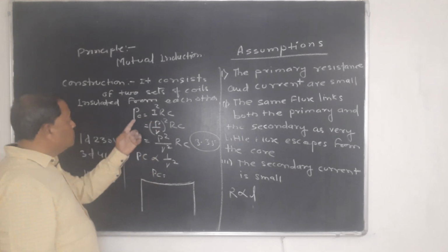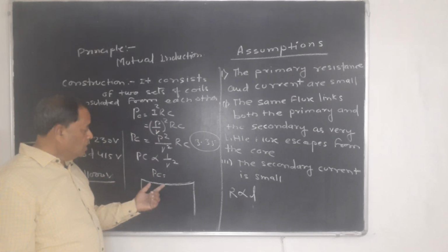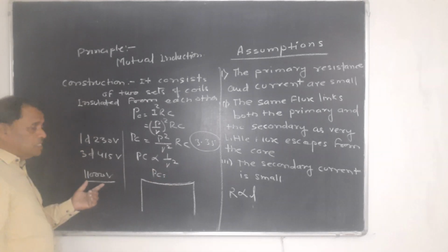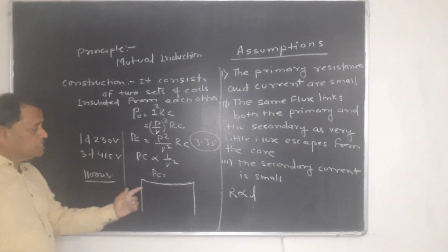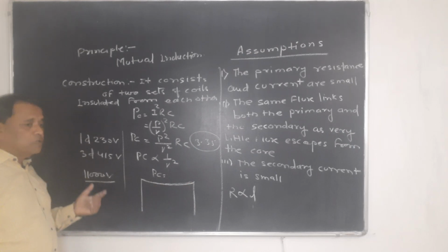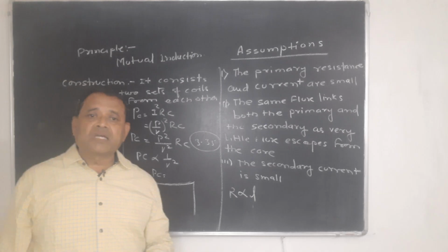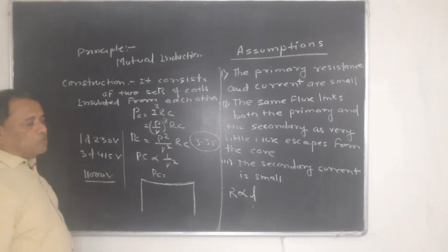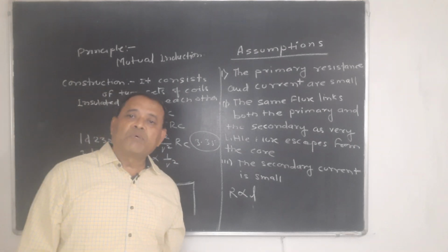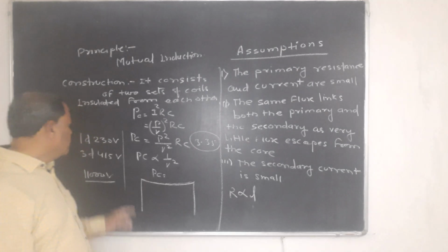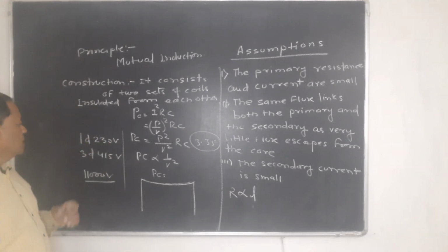So to minimize this Pc waste of power in the system, we have to increase the voltage. As the distance goes on increasing, we also have to increase the voltage: 11,000, 22,000, 33,000 and so on. On the other hand, our residential, commercial or industrial connections are powered with single phase 230 volts and three phase 415 volts.